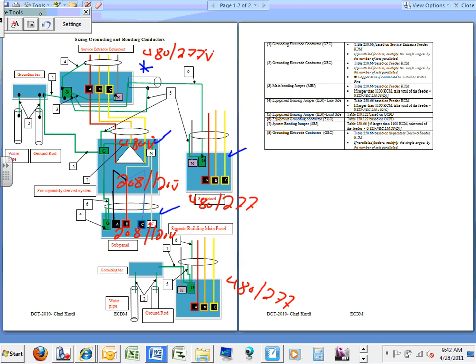I'm going to start reading with the numbers, what the numbers mean, guys. If you look at number one, if you look at the back of the page that I gave you, number one, which is this one here, is the grounding electrode conductor. We size it based on Table 250.66, based on the service entrance conductors coming to the building. If you parallel, you have to multiply the service conductors by how many runs you have.